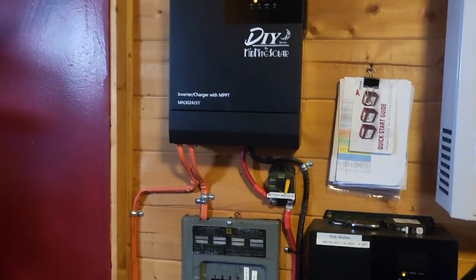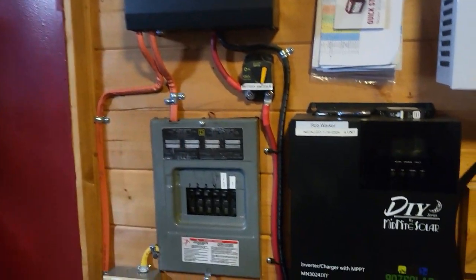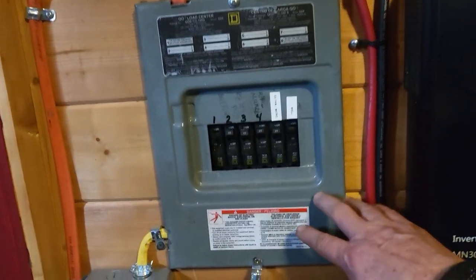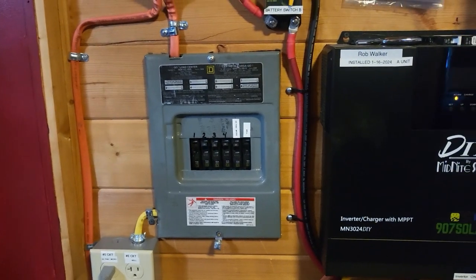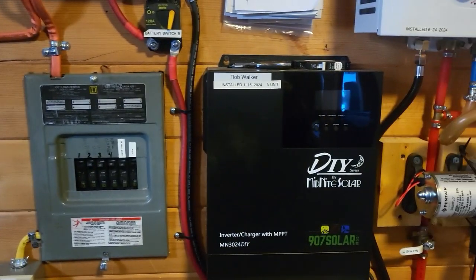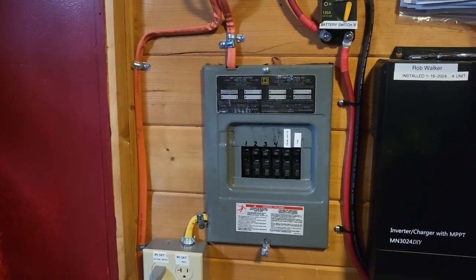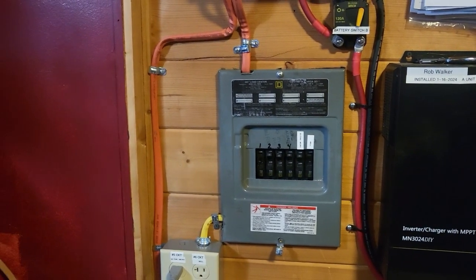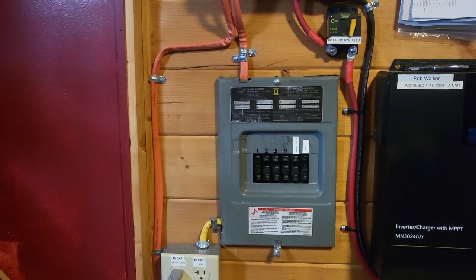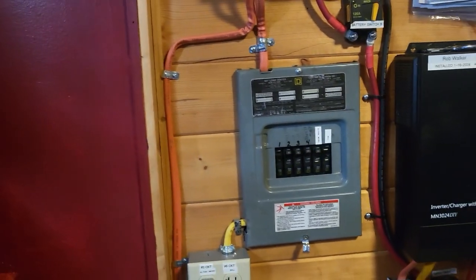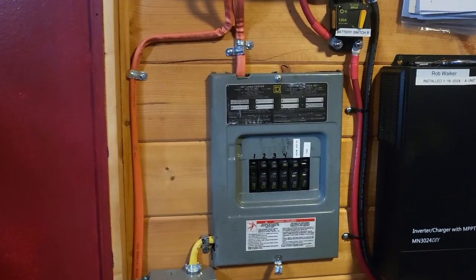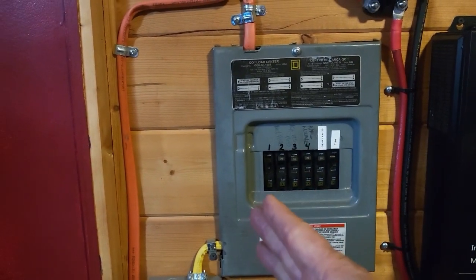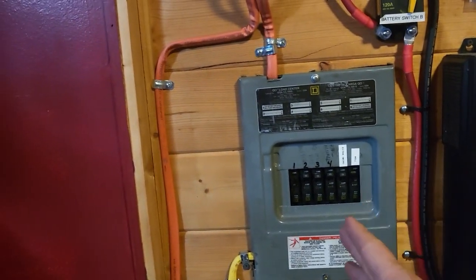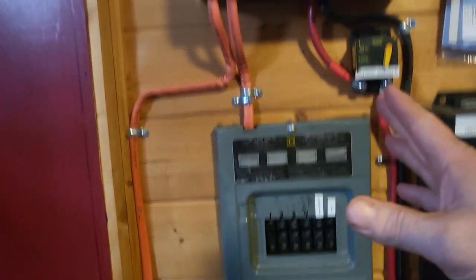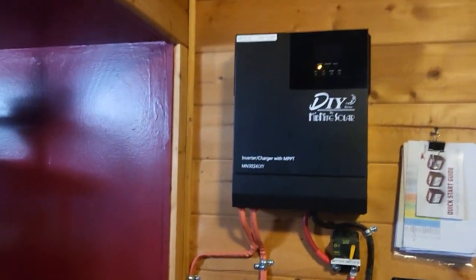If you notice, I have 2 of them, which feed into this panel that was already inside this cabin, pre-wired. So I have an inverter for each phase, L1 and L2, on this panel. It's kind of giving it like 220, but not really 220, because you cannot use a 220 breaker, a double pole breaker, when you have this setup. It will not work. So I essentially have for one phase, L1, each breaker on that, I have an inverter running for that one. And for the L2 phase, all those breakers, I've got this inverter here that supplies power to it.